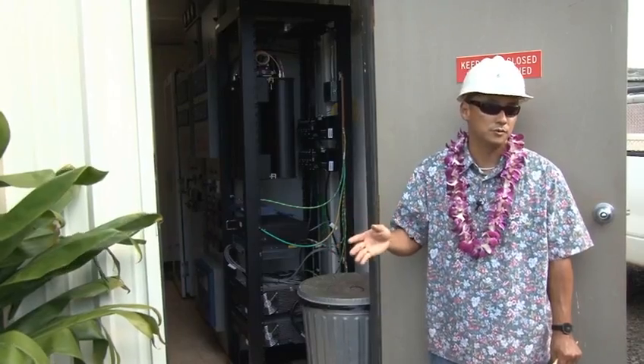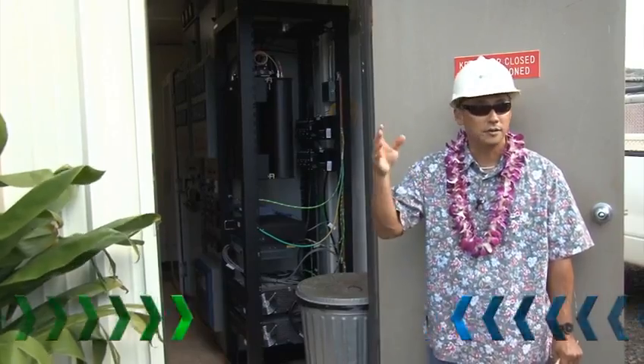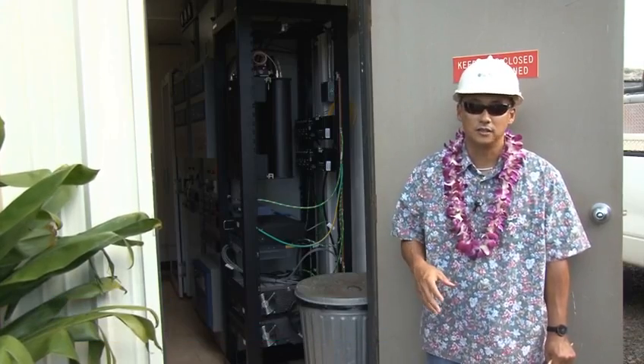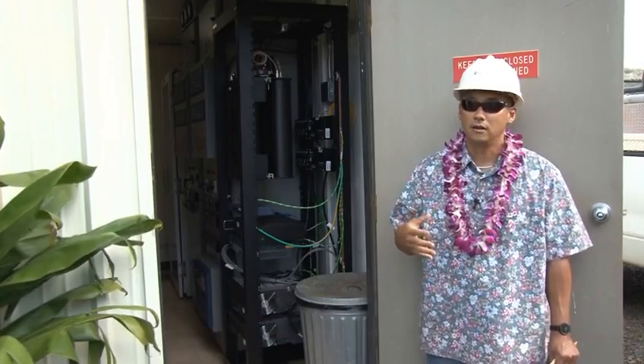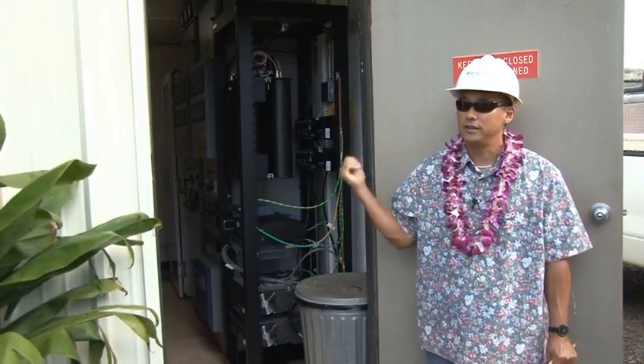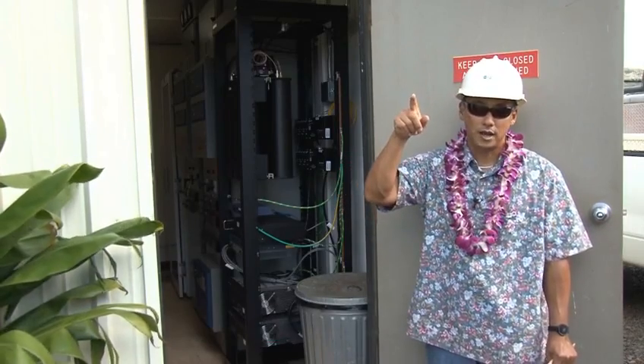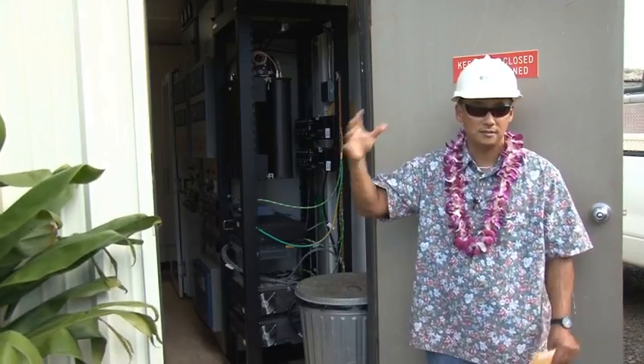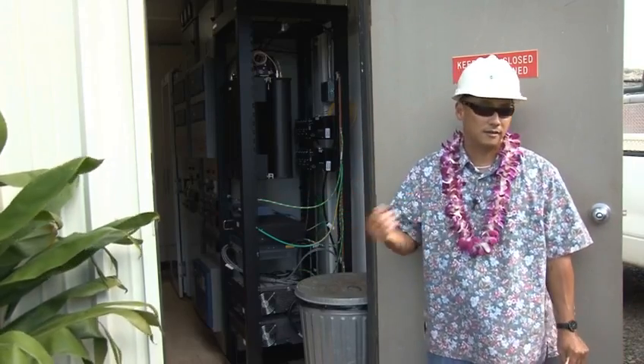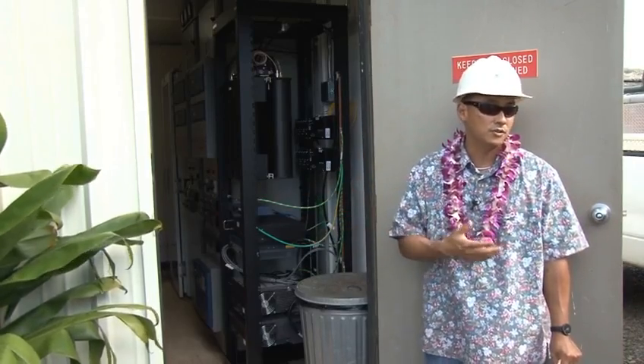We wanted to make sure that we knew that this battery was doing what it's supposed to do during an event. And like I said, we've been capturing events. We're talking about cycles in milliseconds. It's capturing data, so very, very high speed, good resolution. And that's what helped us learn about our system, just these devices. We have one here, we have one at the Port Allen Power Plant, one in Kapaia. These high-speed devices gave us a good sense of what we needed and how this battery would help.